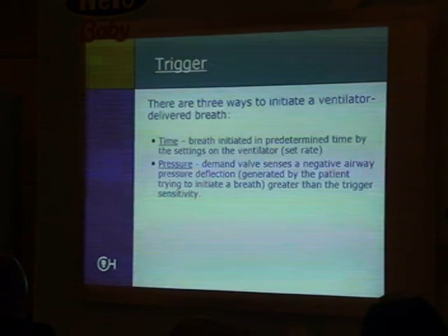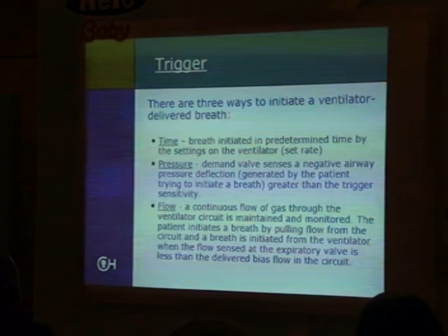The second and final way is by flow. In a lot of our modes, particularly in the neonatal modes, there's a continuous flow of gas that goes through the circuits that's called bias flow. And the ventilator constantly monitors what comes out for bias flow and what comes back to the ventilator through the circuit. So once they pull a certain amount of flow from that bias flow, the ventilator recognizes that there's less flow coming back, and that will deliver a breath. It seems like a slower method, but the process is so quick, and how quickly our ventilators measure doesn't really delay the breath as much as you would think it does. But this, again, would be for a full ventilator breath, or one of the spontaneous breaths with less support.